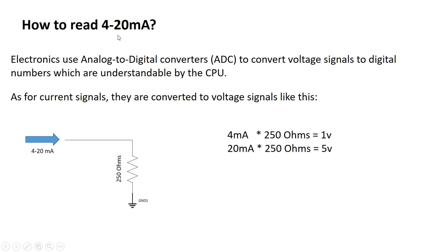But how can the microcontroller or PLC read the current signal? In electronics, we use analog-to-digital converters to convert voltage signals to digital numbers which are understandable by the CPU. Now, as for current signals, they are converted to voltage signals like this. This is the measuring device - it has a 250 ohm resistor. Now when 4 milliamps times 250 ohms equals 1 volt, and 20 milliamps times 250 ohms equals 5 volts, and this goes to the analog-to-digital converter for conversion.